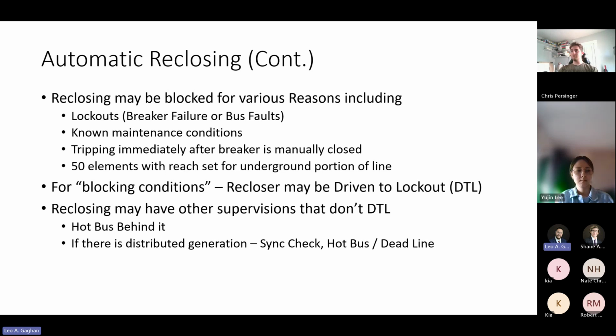And to go back to what we were talking about, this is really just applying to overhead distribution lines today. There's a lot of situations where you don't want to reclose, and a lot of situations where you will actually block closing or reclosing. One would be lockouts. If you had a breaker failure lockout, you've got a bad breaker, you don't want to reclose. The bus fault that we talked about, it's in the yard, so it's unlikely that it's a temporary condition like vegetation or lightning. It could be a boom, someone in a boom. Don't want to reclose for that.